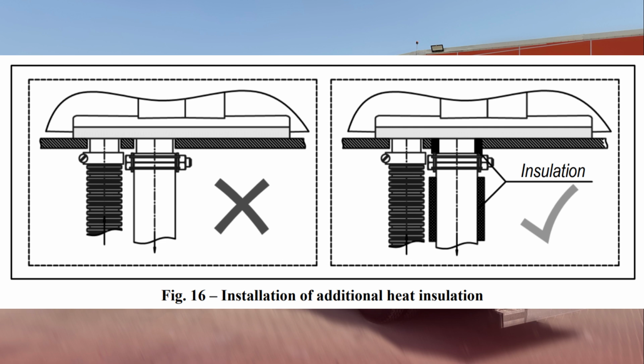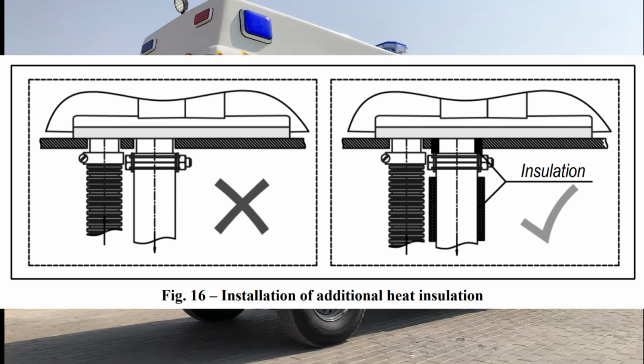It is highly recommended to install the exhaust gas discharge system in such a way that does not allow the exhaust gases to flow inside areas used by people, such as the driver's cabin or the living quarters of a maritime vessel, away from open windows and doors, to avoid the possibility of inhaling dangerous exhaust gases. Do not place the output opening of the exhaust pipe in front of the incoming airflow of the moving vehicle or vessel, as shown in Figure 8.